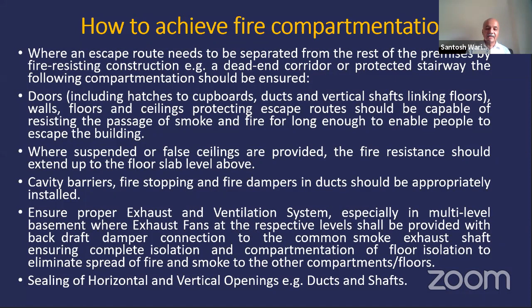Second, the ventilation system is very important for the basement, which was also touched upon by V. Suresh sir, wherein you should have a fire rated ducting system passing through. There are 3 or 4 levels of basement now available. There are cutouts provided from where you can have the exhaust for each independent basement, and the hot heat and smoke are taken out and sent to the environment through the exhaust system. But this system should be totally fire rated. All ducting, everything, fans should have a fire resistance rating, so that heat and smoke will not communicate with the other basements, and you can have proper fire dampers also if it is mechanically ventilated.